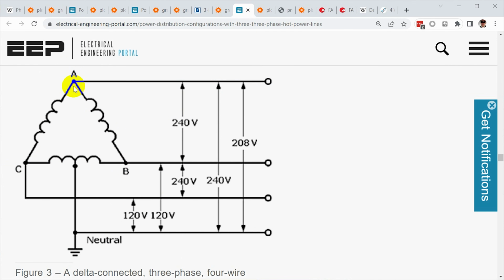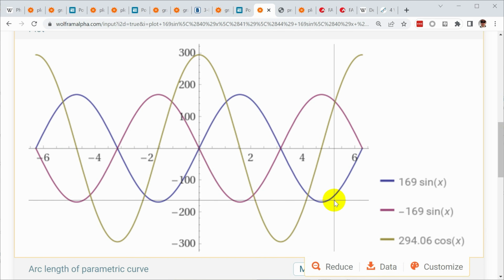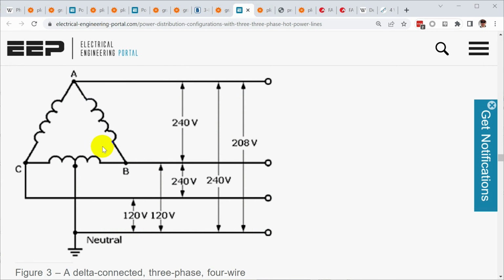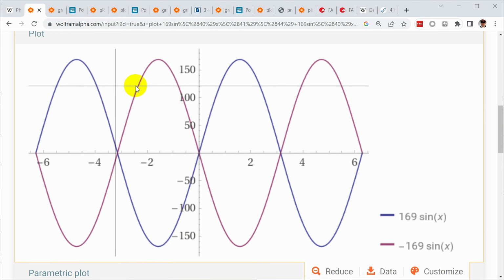It's generating this third leg, also called a high leg or a wild leg, to complete the three legs of the three-phase output. What happens if you grab a meter and start measuring this? Well, you will see something that looks like this. Since you're measuring everything with respect to neutral, if you look at C and B, or A and B, on the phase converter that I have, you will get a plot that looks just like this.